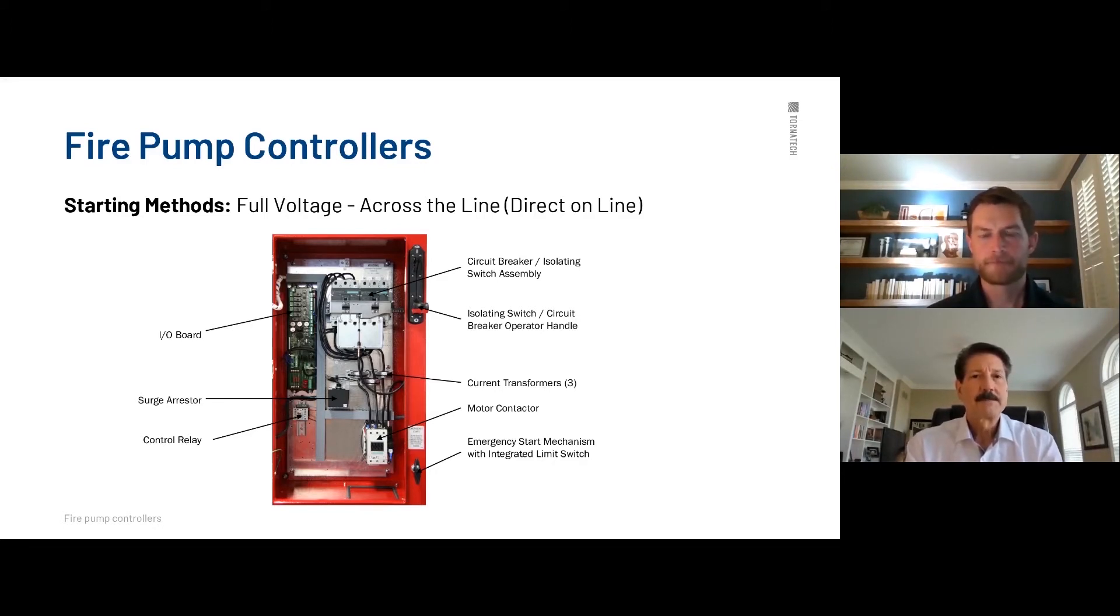You're talking, oh, medium to small to medium horsepower motors. 480 volt, it'd be typical. People ask, where's the tipping point? Well, you might be looking at a 75 horsepower, 480 volt motor for all I know. You know, typically you could use an across the line with no problem, but it's the application you need to look at what will be affected in the facility. This is going to start into when you get into, you know, a hundred horsepower, 125 at 480 volt or bigger. It seems that it's a no brainer that you are going to use a reduced voltage controller. And if it's a 208 volt, you're literally double doubling the full load amperage. And in most cases, the current carrying components will double in size too. Definitely want to start looking at using a reduced voltage on a lower horsepower motor if you're attached to 208 volt.